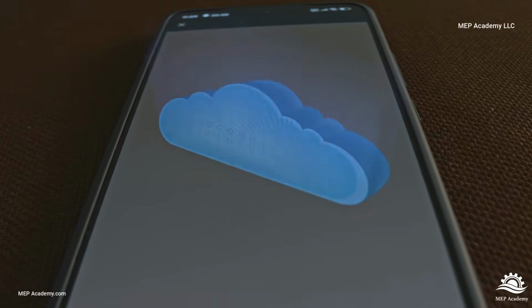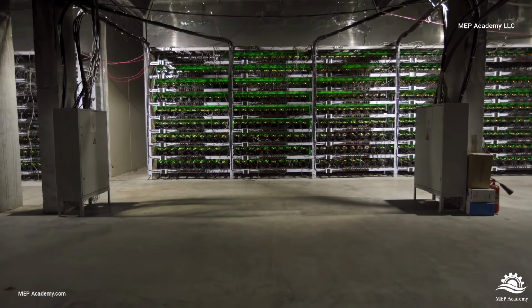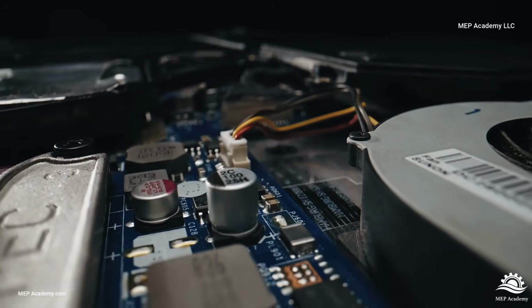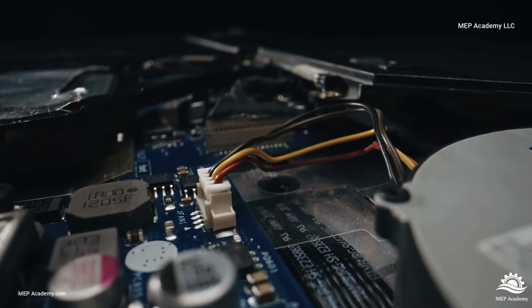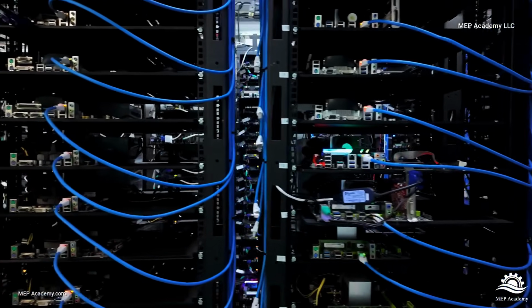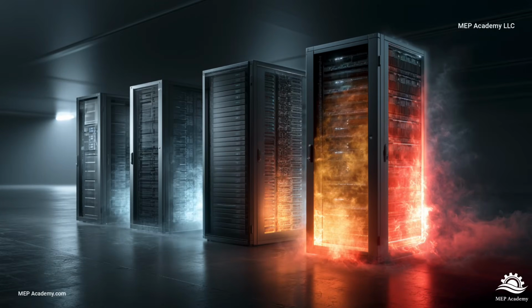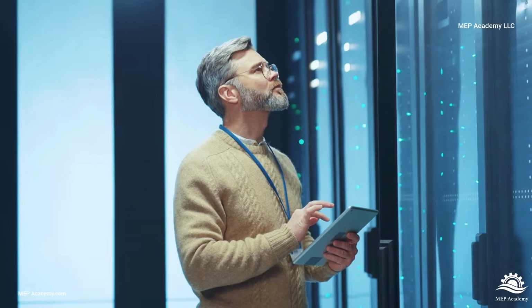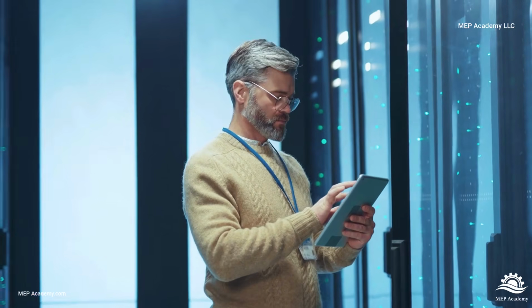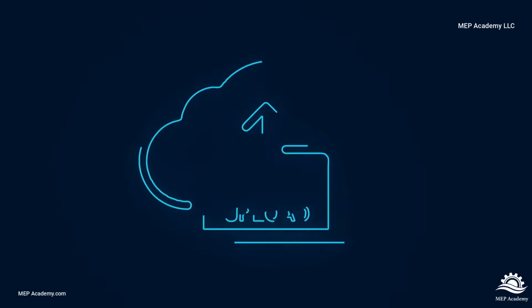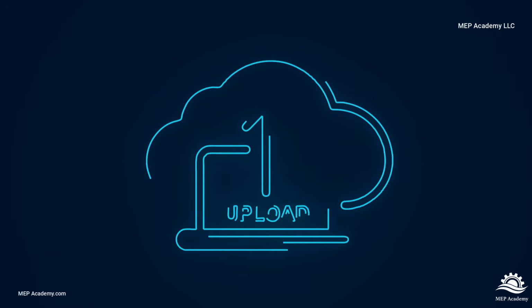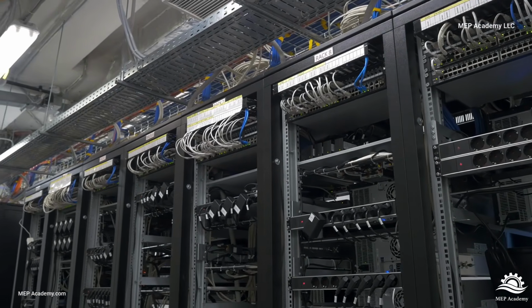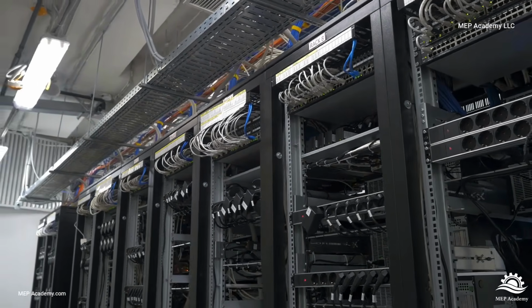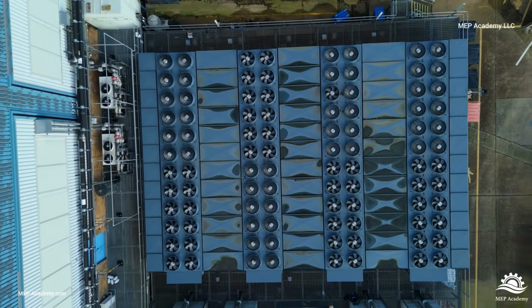The major advantage is efficiency. Instead of cooling the entire room, you're cooling the exact components generating the most heat. This allows much higher rack densities while reducing the amount of airflow required. However, most direct-to-chip systems still require some air cooling. Components that aren't connected to cold plates still need airflow for cooling. As a result, many AI data centers use a hybrid approach combining liquid cooling and air cooling.